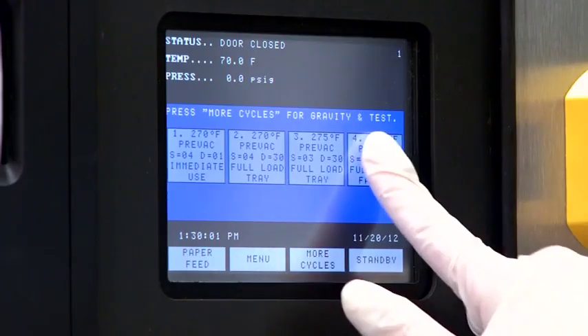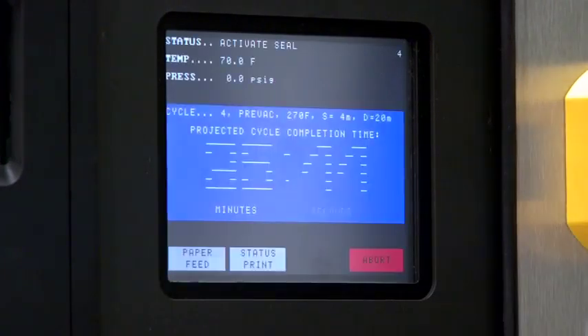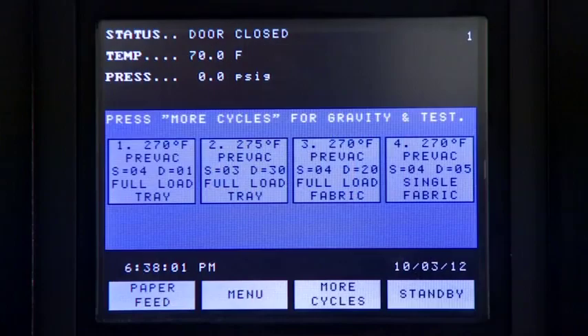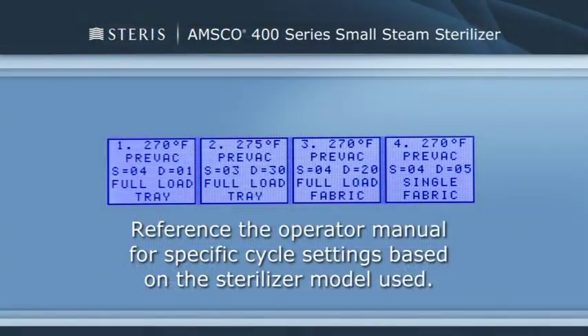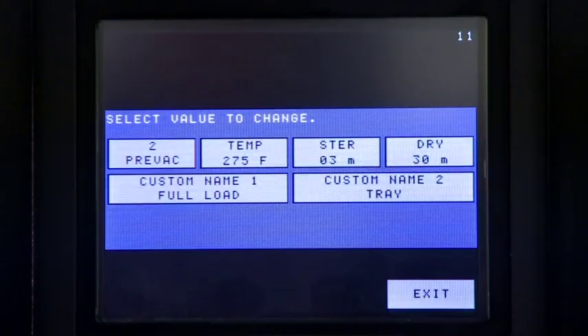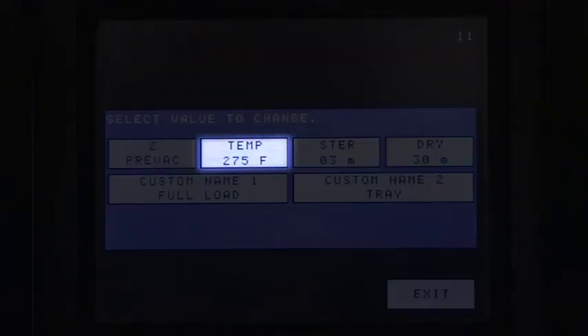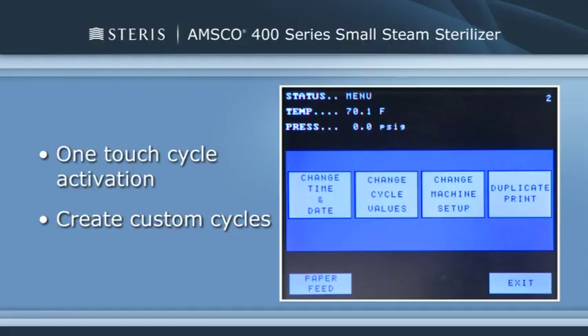The quick, intuitive controls help you choose the cycles you need quickly. The most commonly used cycles come pre-programmed with optimum temperature settings, sterilize times, dry times, and recommended loads. Sterilize temperatures range from 250 to 275 degrees Fahrenheit, which can sterilize a double-wrapped instrument tray of up to 25 pounds in 3 or 4 minutes, with a dry time of 30 minutes.